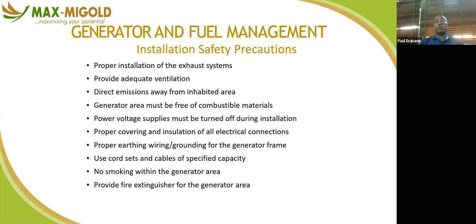Don't, because you are trying to maximize space, put your generator in a closed and tight environment. That won't give cross ventilation. Every now and then you will have overheating of the generator because fresh air is not coming. I mean, a generator needs fresh air just like a human being. The same way, your generator requires fresh air to function well.